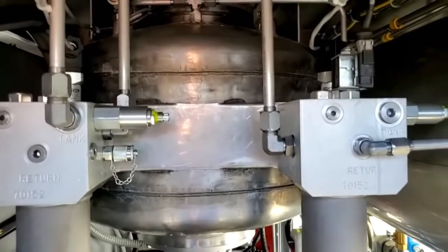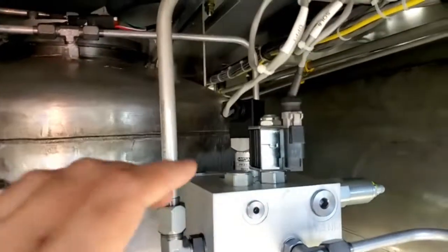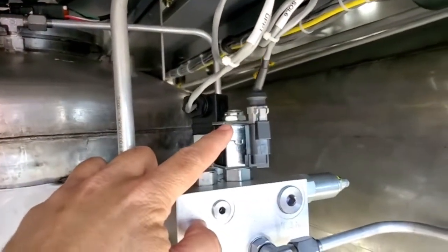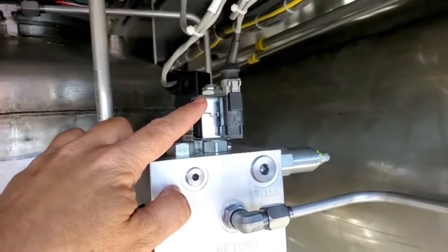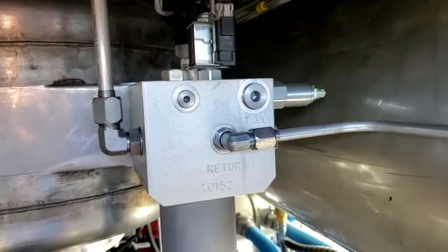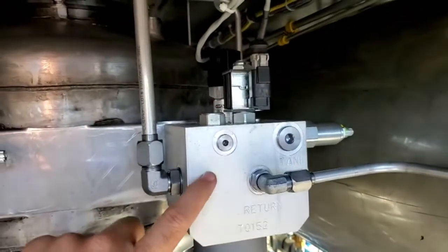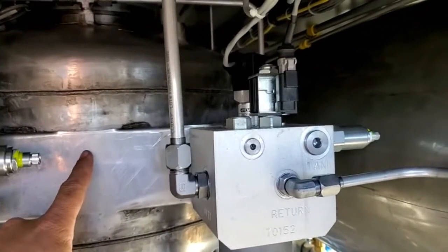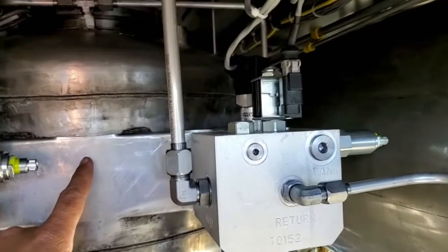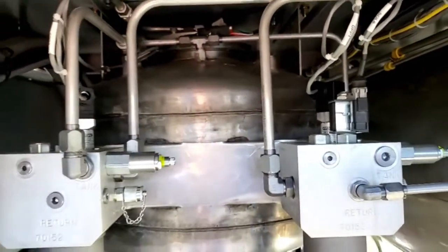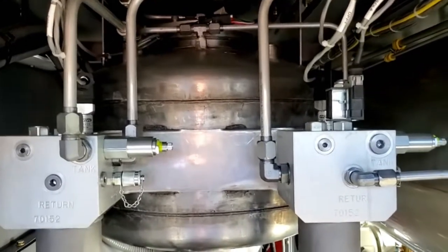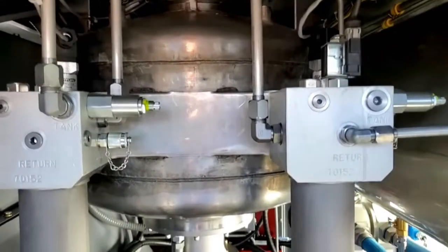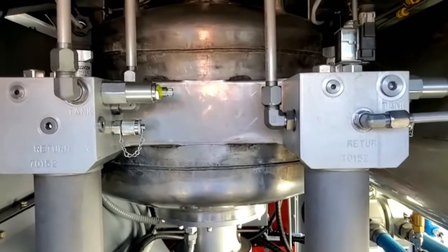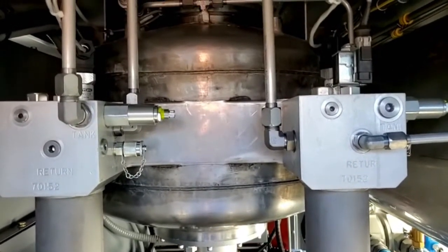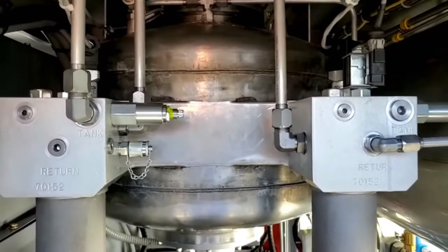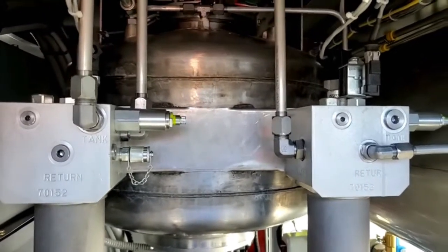Now if the level proceeds up to level 3, you have a solenoid up here that energizes and opens a bypass. So the pressure from the charge pump will start recirculating back to the charge pump through the filter. Fluid will continue to fill into the tank, just not at such a high rate of speed. Once you reach level 4, it triggers an alarm. Your charge pump, your discharge pump, and your vacuum pump all shut off, at which point you'll need to go into your info log screen and manually discharge the tank.